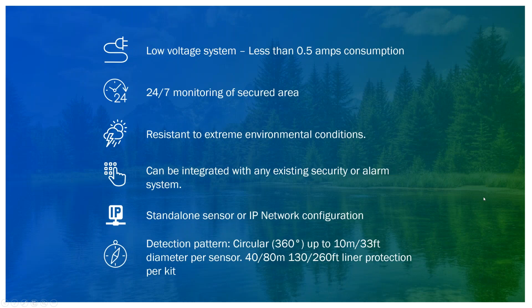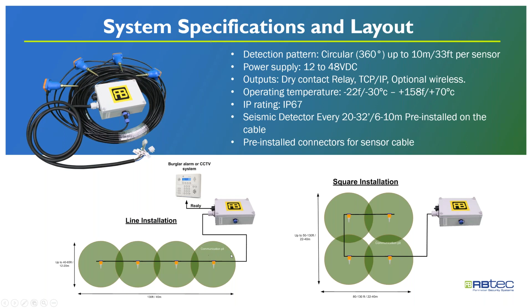You can see the video later on, but the system does not detect dogs or small animals, and therefore won't trigger false alarms from deer, dogs, bears, or anything like that. The system looks like this: you have a processor that can have 4 or 8 sensors connected to it, and each sensor covers roughly 10 meters of detection. So the basic system is 40 meters or 80 meters.